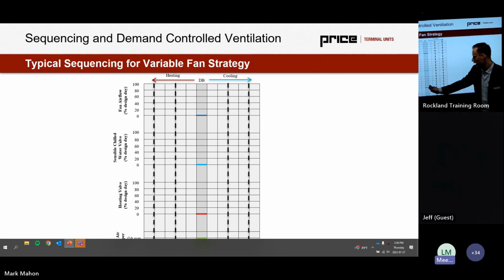So the middle of this diagram is our temperature set point. As we move 1.5 to 2.5 degrees to the right and the left, that's the end of our dead band. So that's where we don't want the system to start cooling or start heating. We're allowing some drift because the occupant probably can't actually tell 2 degrees of difference. So whether it's 70 or 72, who cares? Whether it's 72 or 74, who cares? If our set point's 72, we're going to let it drift a bit. And that's going to allow for really less switching of electrical and mechanical components, which is going to improve lifespan of the building, and it's also going to reduce energy costs for the owner.